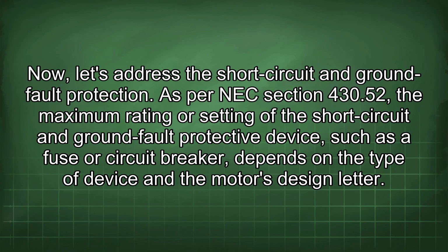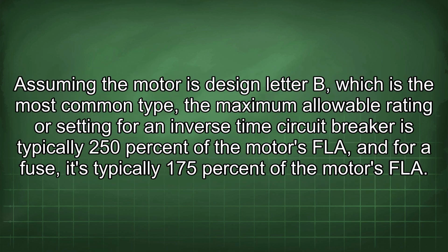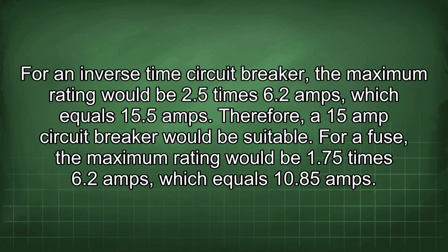Now let's address the short circuit and ground fault protection. As per NEC section 430.52, the maximum rating or setting of the short circuit and ground fault protective device, such as a fuse or circuit breaker, depends on the type of device and the motor's design letter. Assuming the motor is design letter B, which is the most common type, the maximum allowable rating or setting for an inverse time circuit breaker is typically 250% of the motor's FLA, and for a fuse is typically 175% of the motor's FLA. For an inverse time circuit breaker, the maximum rating would be 2.5 times 6.2 amps, which equals 15.5 amps. Therefore, a 15 amp circuit breaker would be suitable.